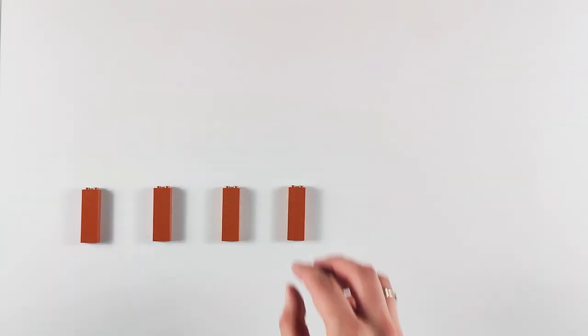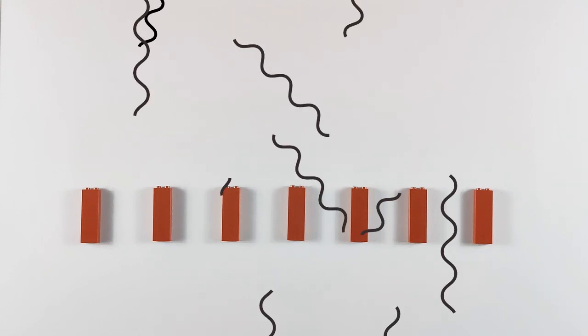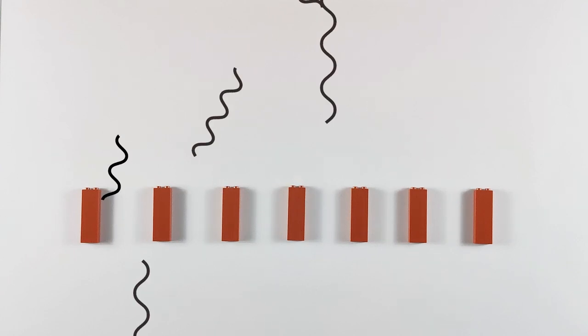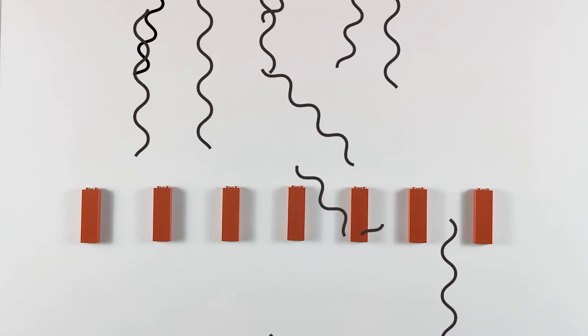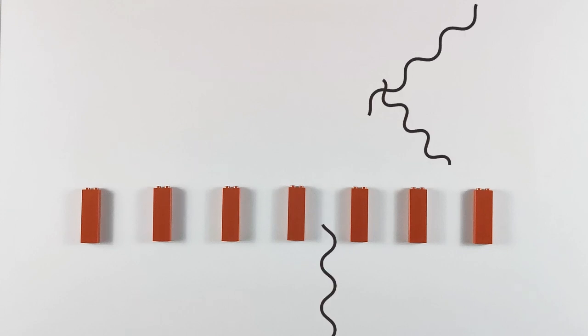We can use anti-scatter grids. Their task is to let through only the photons that fall in the original beam's direction and stop the ones that fly somewhere else. They're like border guards for photons, guarding access to the film. It's interesting that although the anti-scatter grids are often used, actually they weaken the x-ray beam very much, so the dose needs to be increased to obtain a clear image.